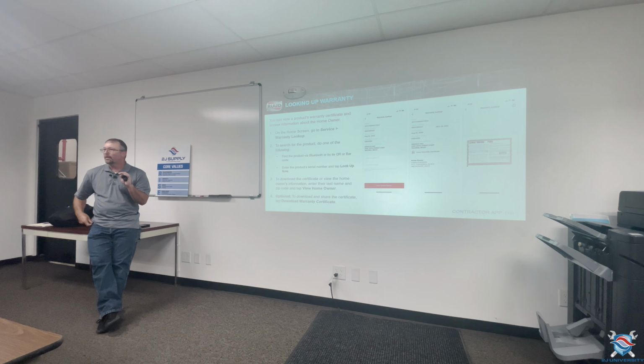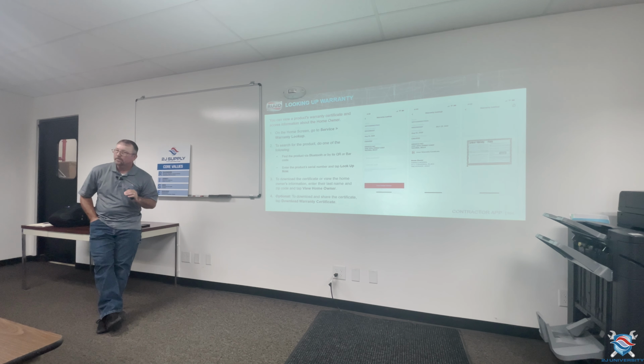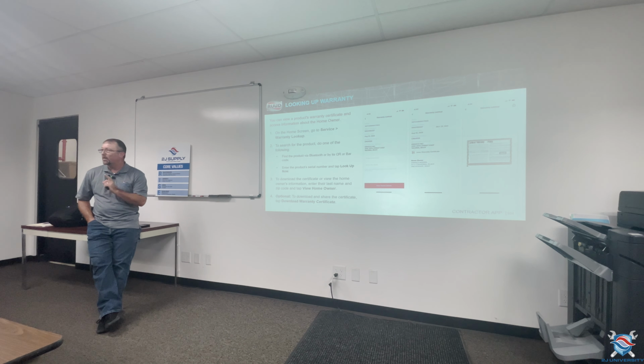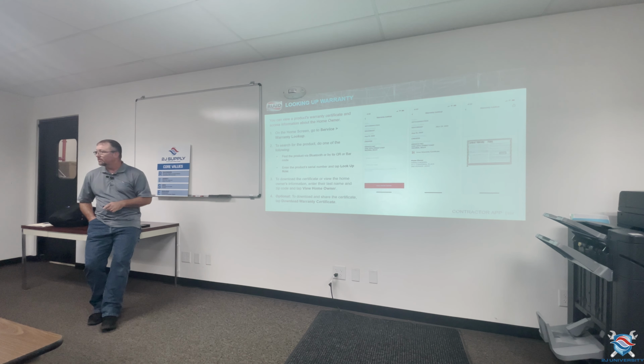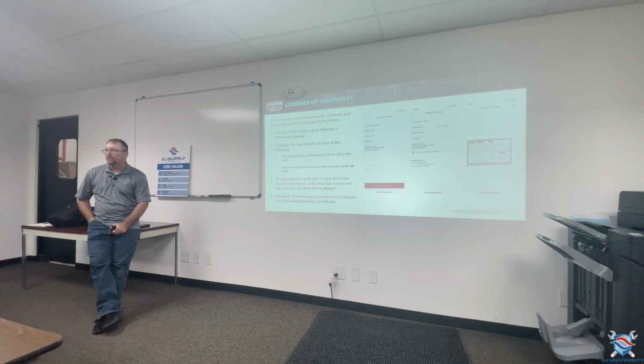Anything 15 SEER or higher AC has to be an AHRI matched and warranted as a system. On the heat pump side, everything has to be warranted as a complete system. There are no coil or heat pump only matches currently. Not to say that won't change, but everything currently is a match system. So if you're doing a dual fuel system, you have to have a match system. It has to be furnace, coil, outdoor unit matched.